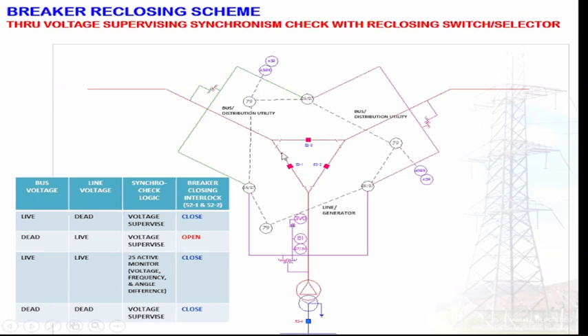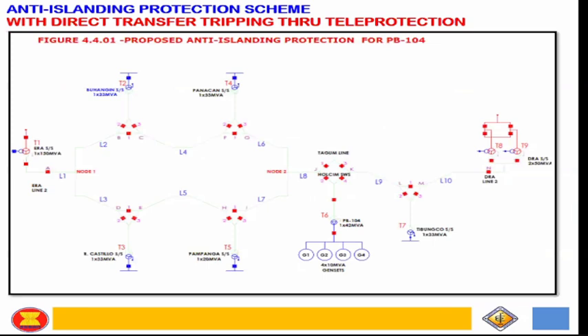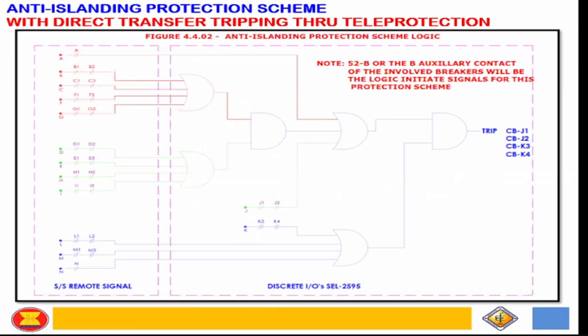Also, ensuring this in reclosing: that is one of the requirements for restoring the distributed generation, ensuring the safety of its restoration by synchronizing with the system. And also this anti-islanding protection. It looks at the statuses of the breakers, for example, if this is the DG and the power barges, whether the connected switching stations and their breakers are open. With this logic, they interpret it as a loss of connection: the adjacent breakers are open, so I will trip.